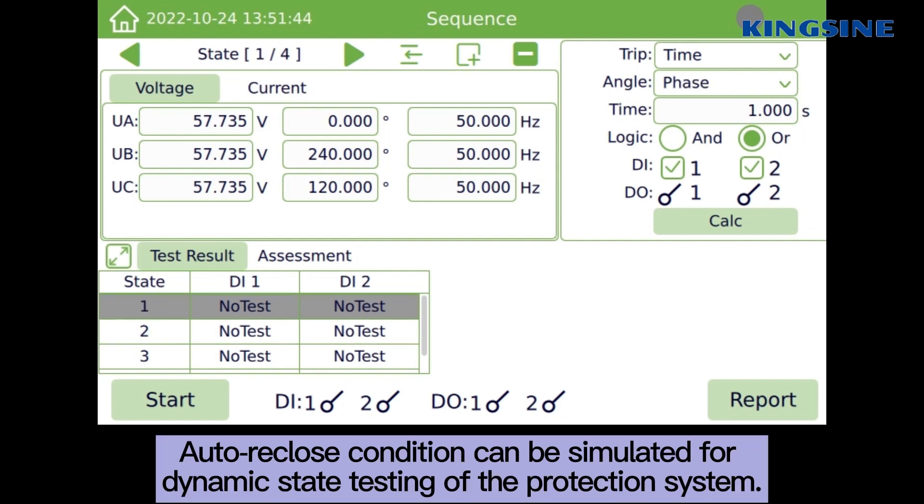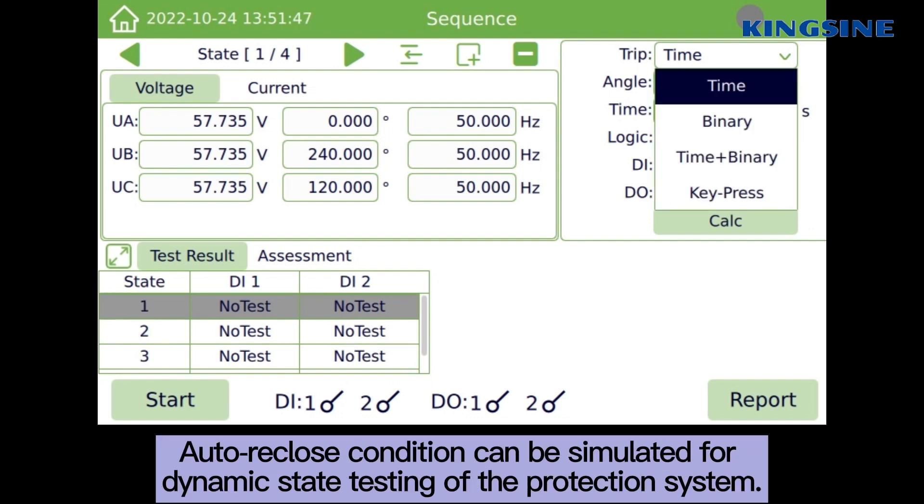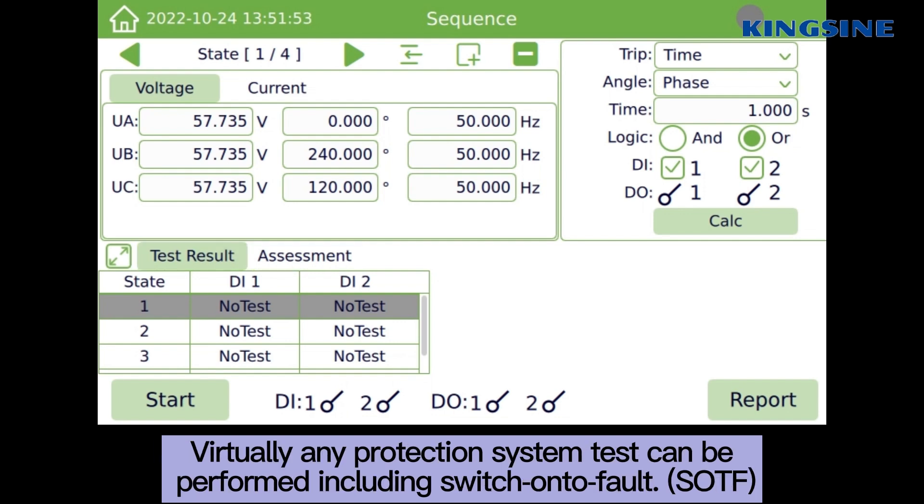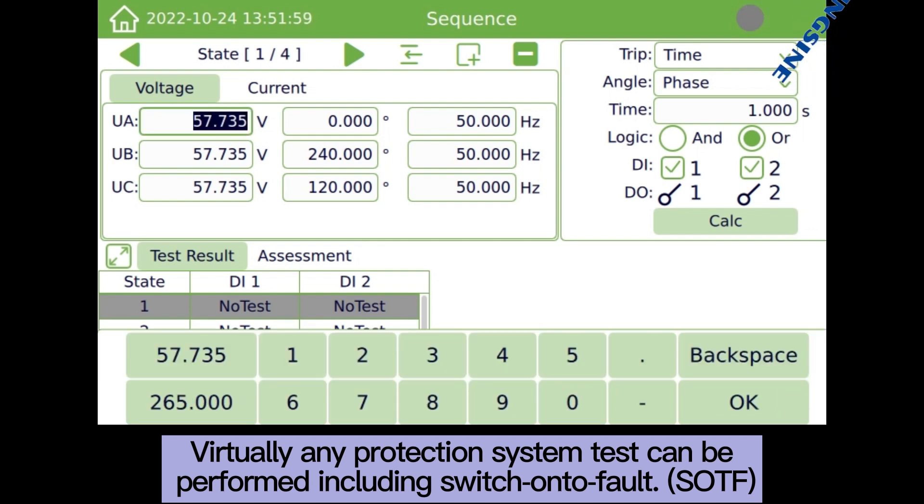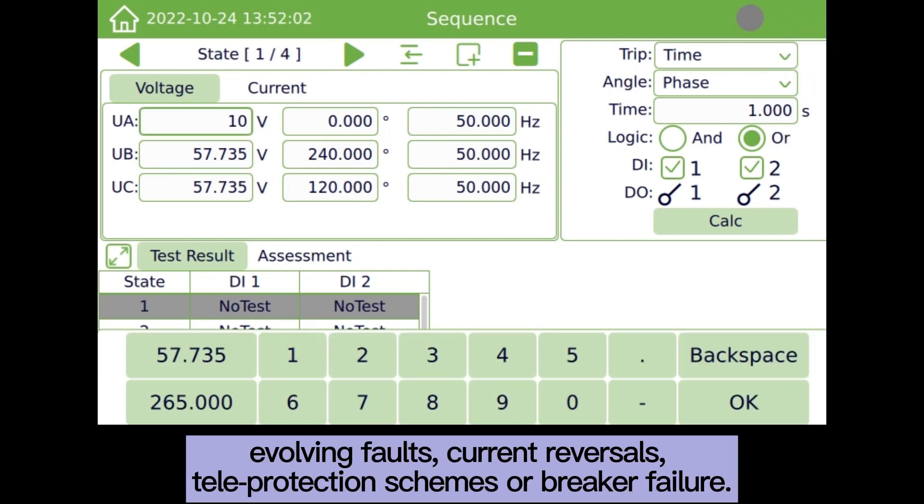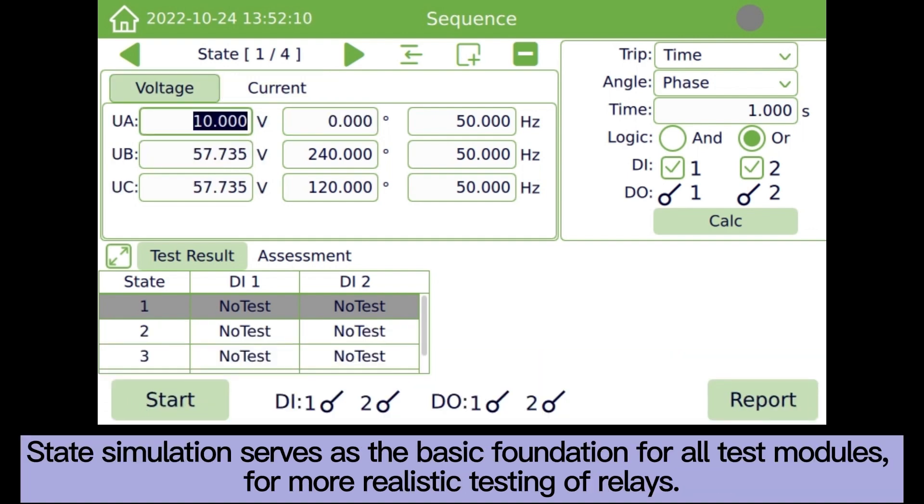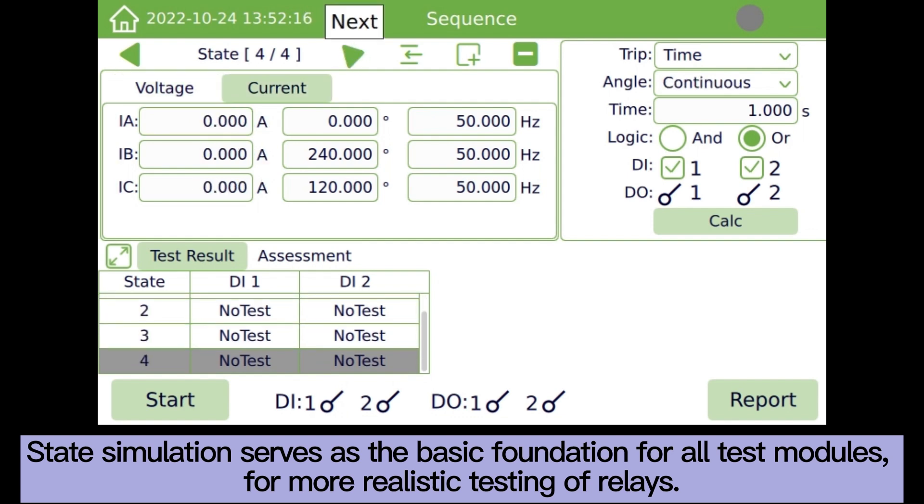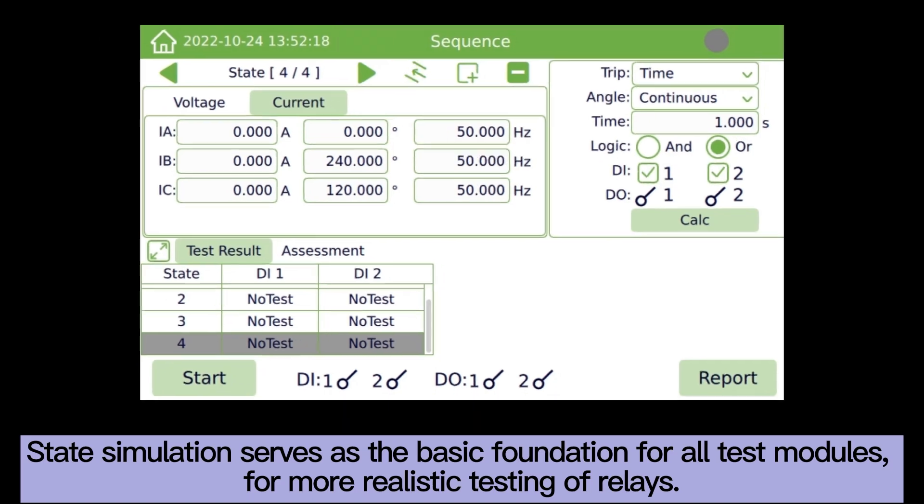Auto-reclose condition can be simulated for dynamic state testing of the protection system. Virtually any protection system test can be performed including switch-on to fault, evolving faults, current reversals, tele-protection schemes, or breaker failure. State simulation serves as the basic foundation for all test modules for more realistic testing of relays.